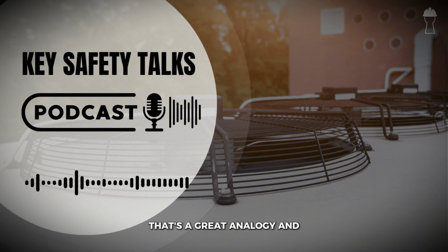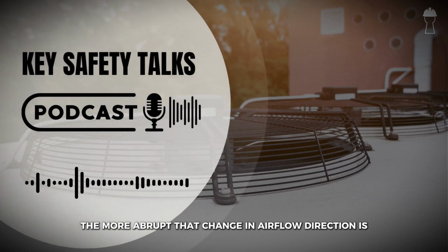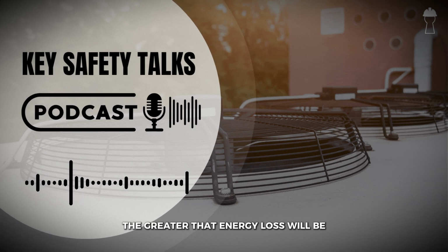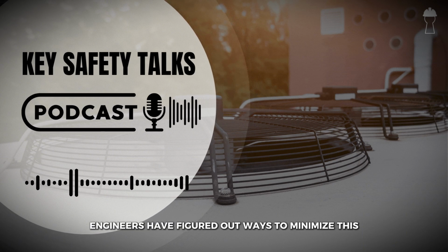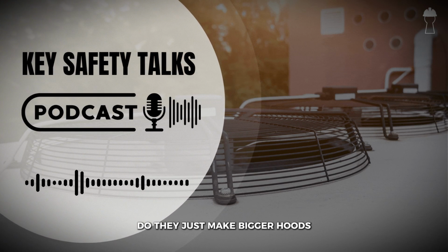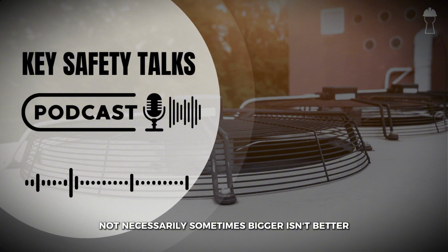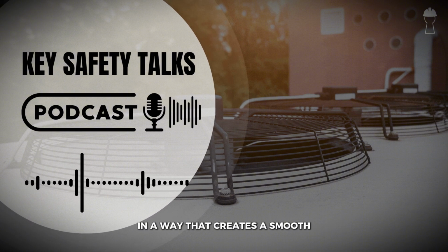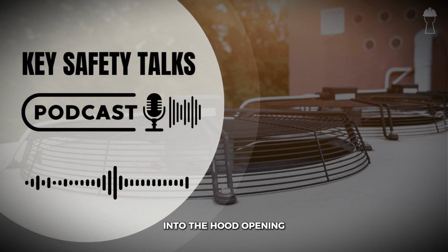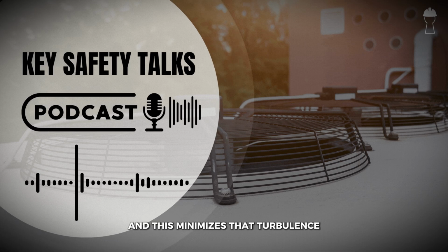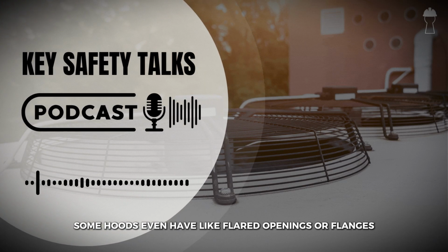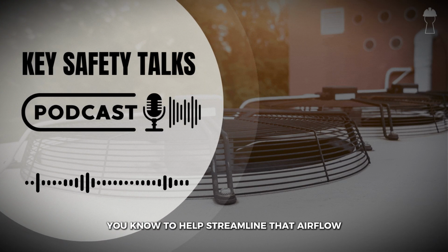That's a great analogy. And the more abrupt that change in airflow direction is, and the smaller the hood opening, the greater that energy loss will be. But luckily, engineers have figured out ways to minimize this. Oh, that's good. So how do they make the system more efficient? Do they just make bigger hoods? Not necessarily. Sometimes bigger isn't better. It's more about designing the hood in a way that creates a smooth, gradual transition from the surrounding air into the hood opening. And this minimizes that turbulence and reduces that energy loss. Some hoods even have flared openings or flanges to help streamline that airflow.